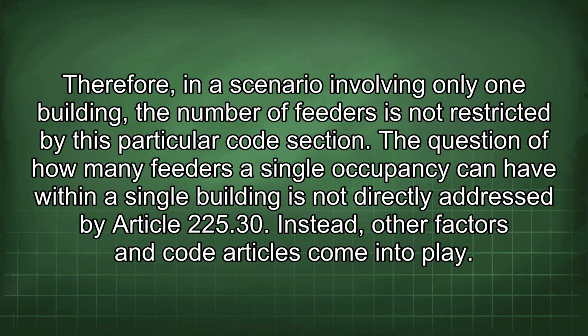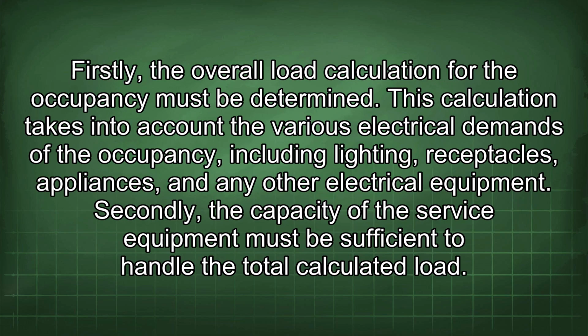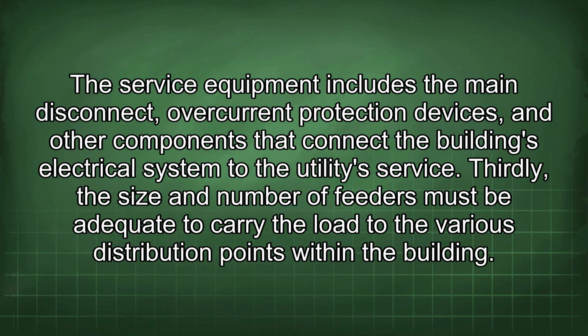The question of how many feeders a single occupancy can have within a single building is not directly addressed by Article 225.30. Instead, other factors and code articles come into play. Firstly, the overall load calculation for the occupancy must be determined. This calculation takes into account the various electrical demands of the occupancy, including lighting, receptacles, appliances, and any other electrical equipment. Secondly, the capacity of the service equipment must be sufficient to handle the total calculated load. The service equipment includes the main disconnect, overcurrent protection devices, and other components that connect the building's electrical system to the utility service. Thirdly, the size and number of feeders must be adequate to carry the load to the various distribution points within the building.